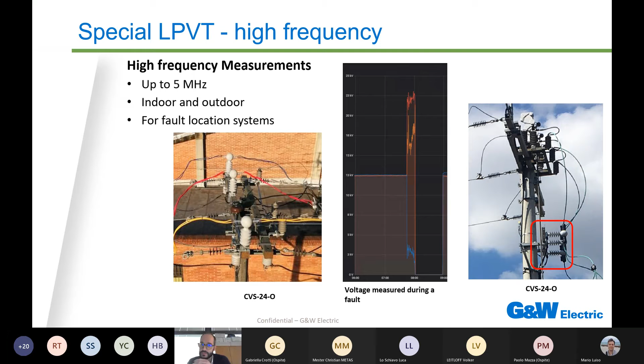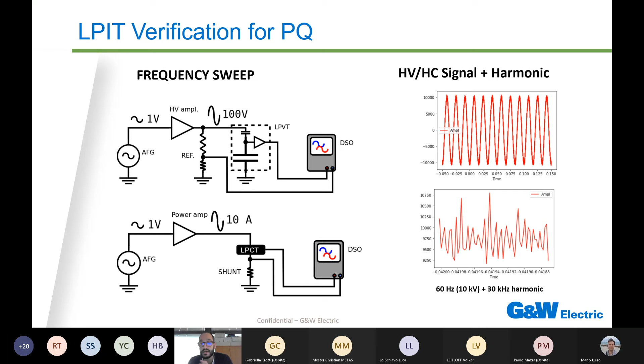In-house, we do a frequency sweep. We impose a frequency component, which could be voltage or current. We measure it with a reference that has a bandwidth wide enough, and we compare our sensor to this measurement. But also in an external laboratory, we impose a high voltage or current signal and add some harmonics to it. For example, on the left, we imposed 10 kV at 60 Hz plus a small 30 kilohertz harmonic. And in some preliminary analysis, we found that the results are quite comparable.